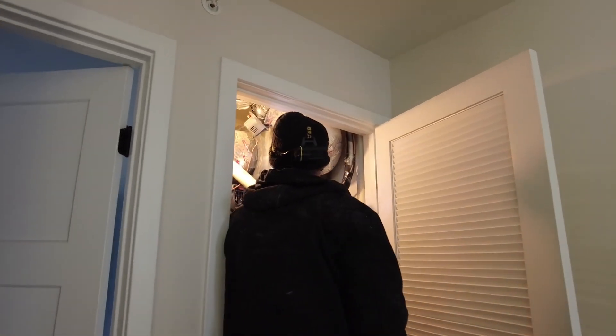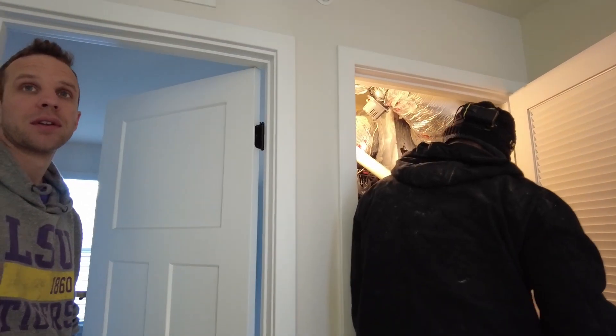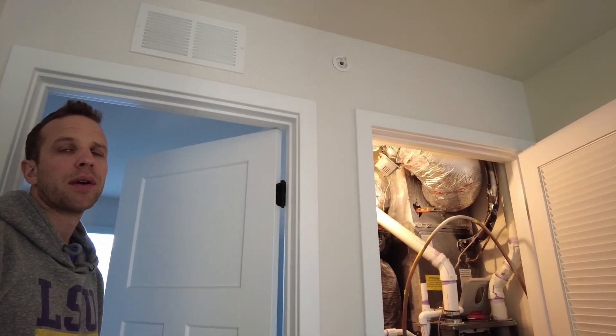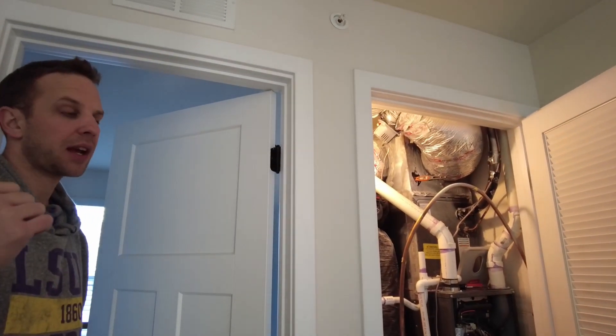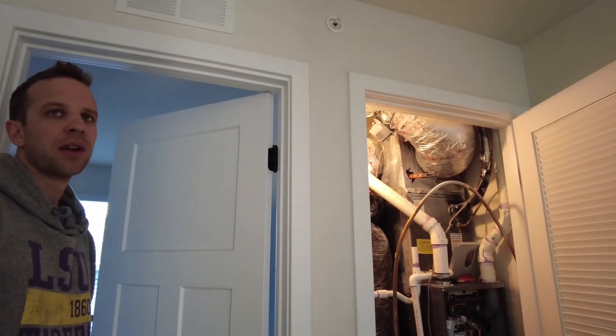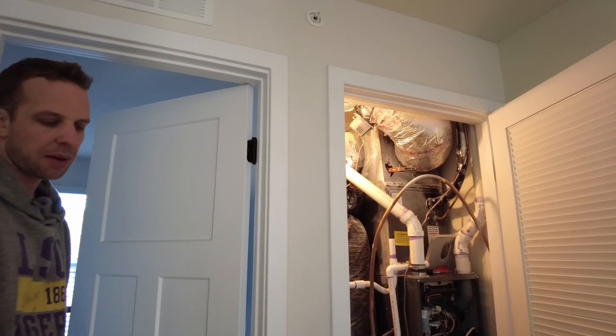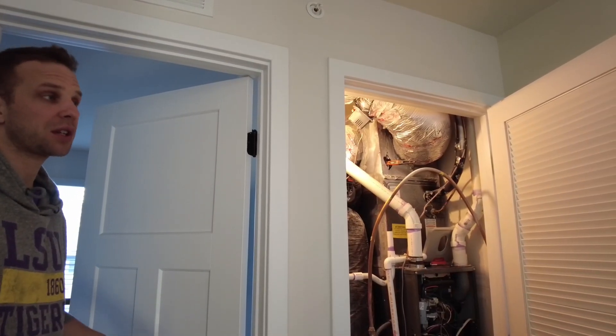As for filter frequency, I replace these probably every four or five months or when they tell me to. With one-inch filters you definitely want to check them at least once a month — if they look pretty impacted after a month, replace them. I usually recommend replacing one-inch filters once a month regardless. The lower floor filter was okay, not really dirty at all. The mid-level one was pretty bad — there was a lot of construction dust, so the first few I changed here were nightmares.